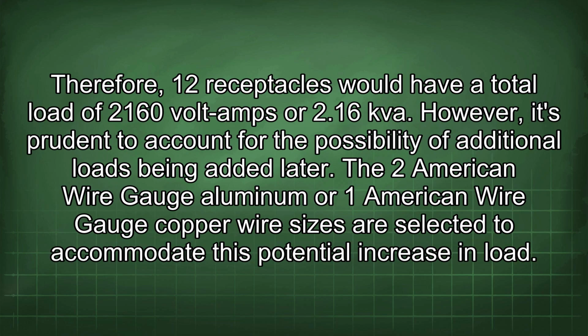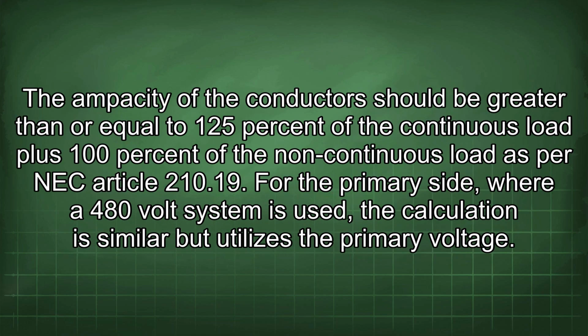Therefore, 12 receptacles would have a total load of 2160 volt amps or 2.16 kVA. However, it's prudent to account for the possibility of additional loads being added later. The 2 American wire gauge aluminum or 1 American wire gauge copper wire sizes are selected to accommodate this potential increase in load. The ampacity of the conductors should be greater than or equal to 125% of the continuous load plus 100% of the non-continuous load as per NEC Article 210.19.